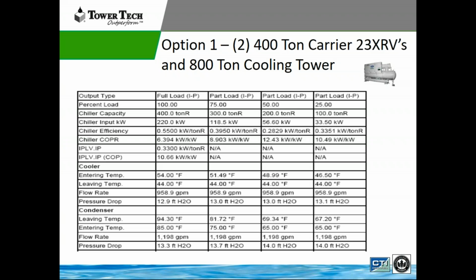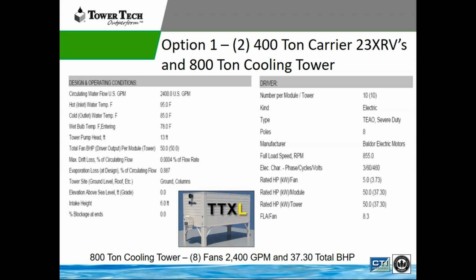So option one is two 400-ton Carrier 23XRVs and an 800-ton cooling tower. And in this case, you can see these 400-ton chillers are ultra high efficiency chillers running at 0.55 kW per ton full load and 0.33 IPLV. The cooling tower itself is an 800-ton cooling tower, 2400 GPM, operating at 37.3 brake horsepower.